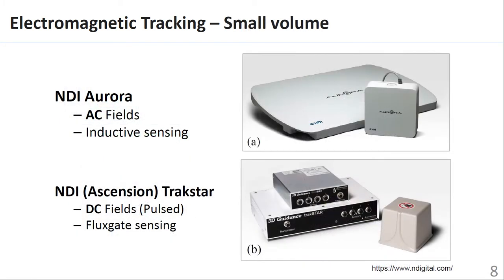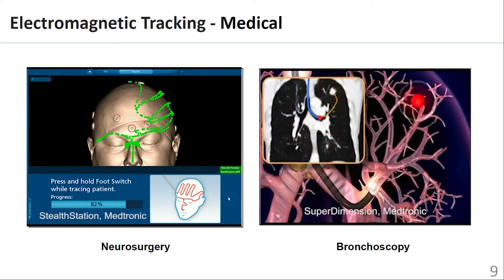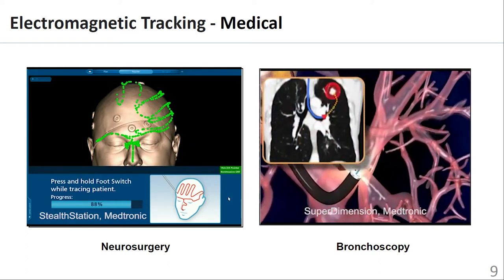Tracking systems such as the Aurora and TrackStar are capable of tracking much smaller magnetic sensors in the order of millimeters in size. The Aurora sensors operate on passive magnetic induction while the TrackStar utilizes active flux gate sensing technology. The smaller sensors and tracking volume make them suitable for medical navigation applications.